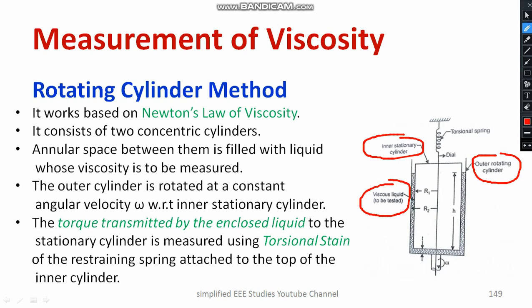The outer cylinder is connected with a shaft which rotates at an angular speed of omega. It is also connected with a torsional spring, as shown in the diagram, and there is a dial and pointer kept along with the spring. The overall device — the rotating cylinder method — works based on the principle of Newton's law of viscosity, which we discussed in the previous session. That means shear stress tau is directly proportional to mu (dynamic viscosity) and du/dy.